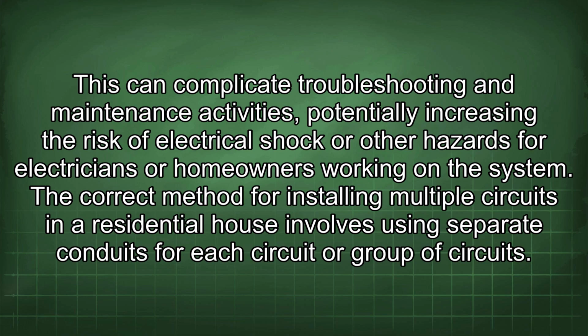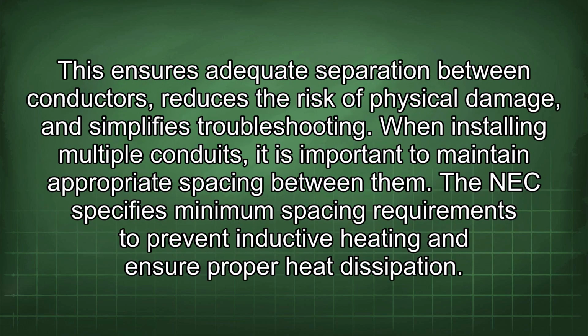The correct method for installing multiple circuits in a residential house involves using separate conduits for each circuit or group of circuits. This ensures adequate separation between conductors, reduces the risk of physical damage, and simplifies troubleshooting. When installing multiple conduits, it is important to maintain appropriate spacing between them. The NEC specifies minimum spacing requirements to prevent inductive heating and ensure proper heat dissipation.